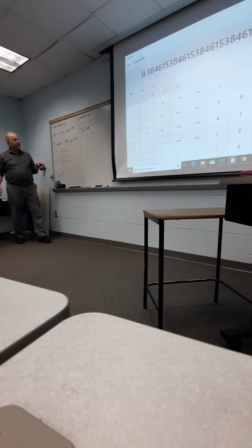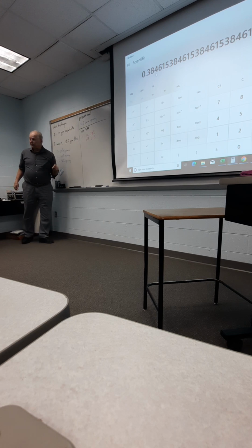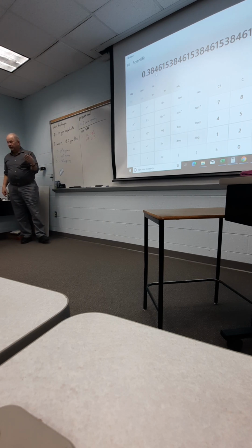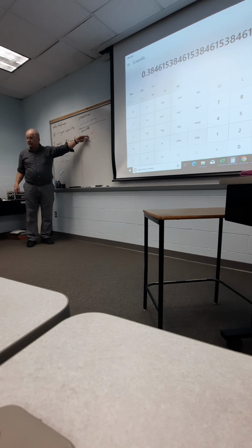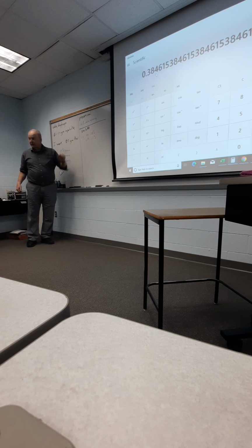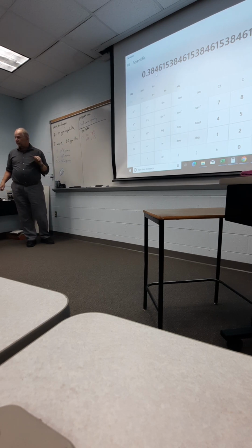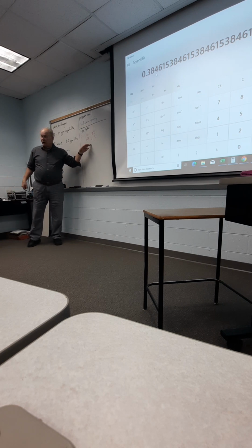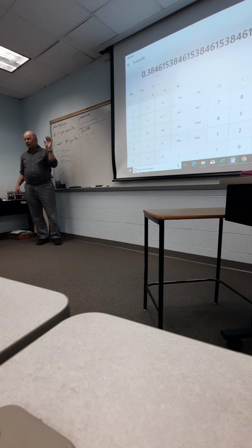Now, of course, this gives us pretty close to 0.5 instantaneously. This clearly does not. This is either 0 or it's 1.3 gallons per minute, but it's duty cycled to give us roughly the same effect as 0.5. Now, if we can tolerate the on-off capability, then all we're looking for is average flow rate, in other words, to say fill a tank. Nothing wrong with this. Works very nicely.